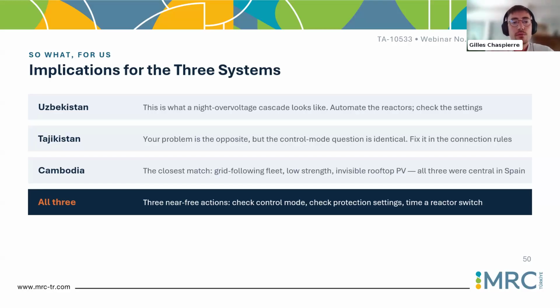So for Uzbekistan specifically, I've learned that you are facing nights, so no PV during the night, but a lightly loaded grid, meaning your grid is capacitive and you can have overvoltage situations. It's important for you to already check the settings of your shunt reactors.